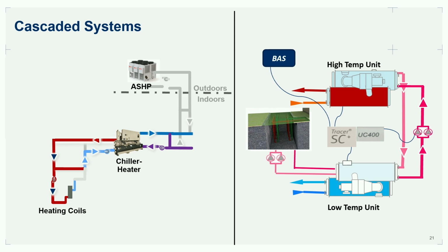So we're pushing a lot of cascaded systems, especially in northern climates on the air source side, where we're dealing with 0 degree ambient or maybe minus 20 degree ambient. We've got equipment that can do 180 degrees of lift at minus 20.